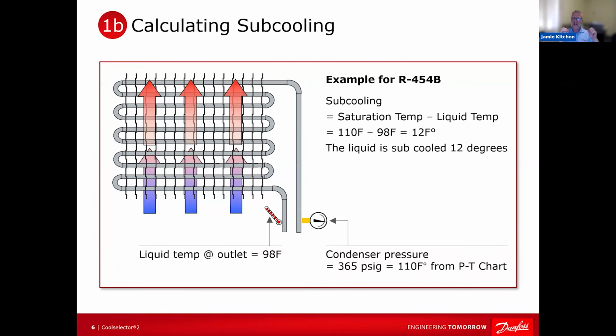Remember, 100% of the heat you're going to reject occurs in the condenser. So the energy in your liquid coming out of the condenser is the same as going into your metering device, is the same as going into your evaporator. Because remember, there's no energy change, BTU per pound wise, in your TXV or your metering device. So subcooling is not just for eliminating flash gas, it also helps make the system more efficient. And it's so important to understand that.